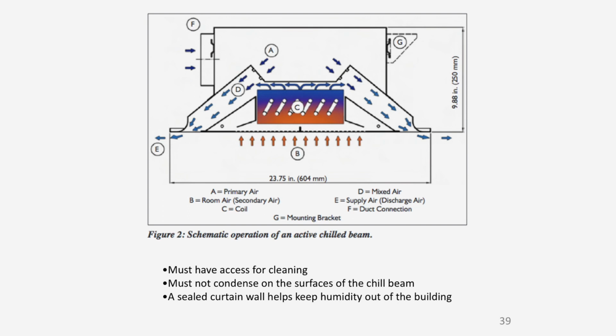Now, the chill beam seems to work quite well if we can keep humidity away from it. Why is that a concern? Because these chill beams recirculate air and will bring lint into that space, and if there's humidity, it's going to condense. This works 95% of the time in my climate, but occasionally we exceed those design limits and get moisture in the building. The criteria we put in require it to be accessible for cleaning, if you clean them once a year, it solves a lot of problems. You're only going to be humid in this climate maybe 2 weeks, about 300 hours a year, when we go a little too high in humidity. So that sealed curtain wall keeps a lot of that out, as well as a good ventilation system.